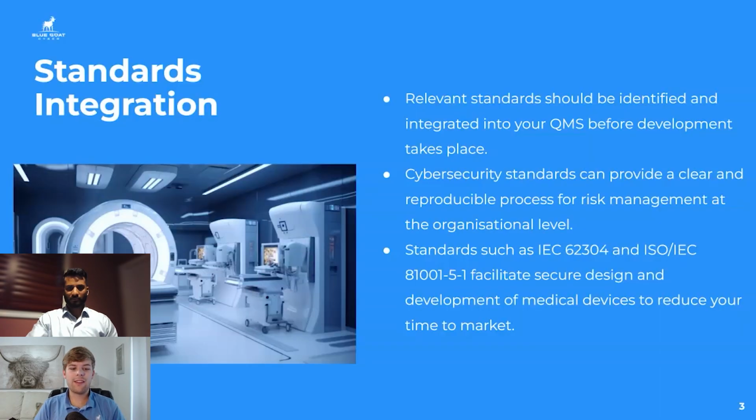All right, now the first thing that I want to talk about before we get into the actual standards is how we can integrate these standards. So relevant standards should be identified early into your quality system before development takes place. And what that means is as we're starting that design process, as we're starting the development process for the medical device, we want to figure out what standards are going to be relevant.